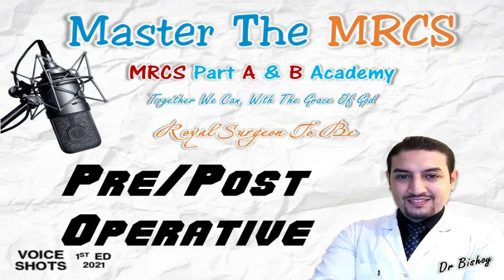Coagulation electrosurgery. It results in formation of a coagulum, from its name. It's a modulated current with intermittent dampened sine wave of high peak voltage. It causes evaporation rather than vaporization, of intracellular fluid, and again it results in formation of coagulum. So coagulation, coagulum, evaporation, modulated current with intermittent dampened sine waves of high peak voltage.